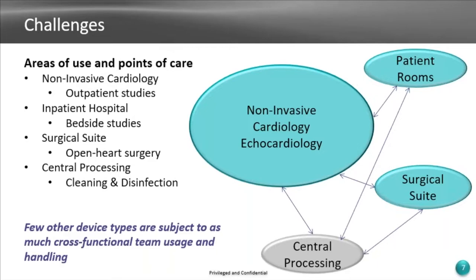The challenge with TE probes is they are constantly being handled. They may be used in cardiology, then get put—hopefully—in an approved container, sometimes a pillowcase or a red bag, and get brought down to SPD or central processing. Then it gets put into another container, sometimes a pillowcase or a green bag, God forbid. Then it goes up for storage, and back to wherever it's going to be used. So there are multiple people handling these devices across multiple departments, and they're always being moved around.